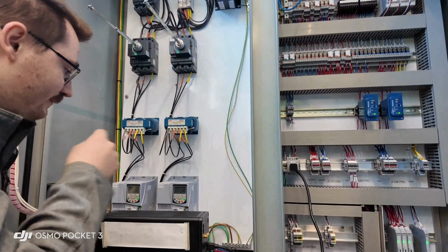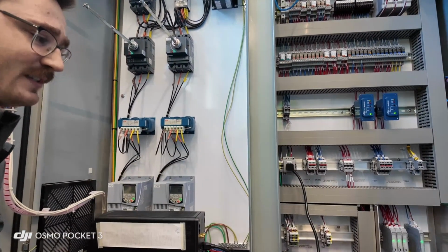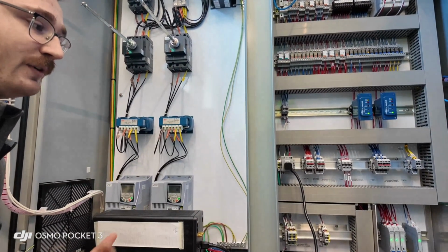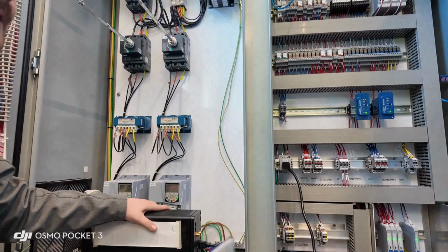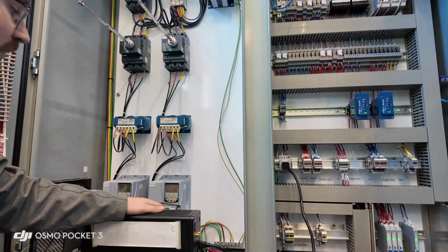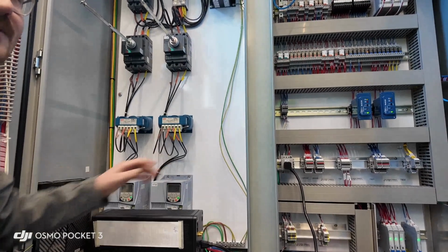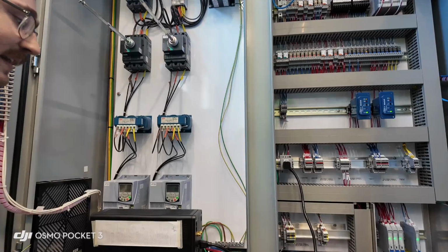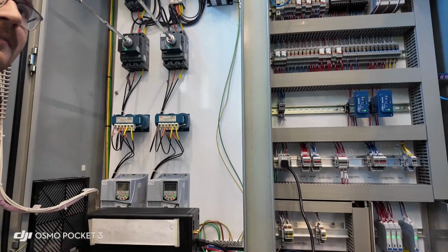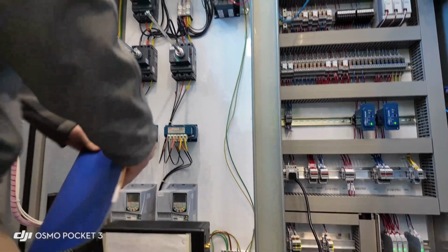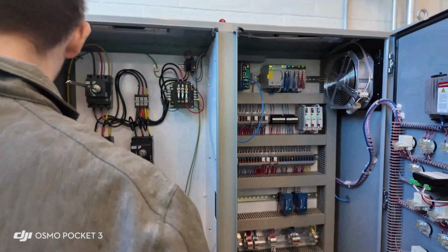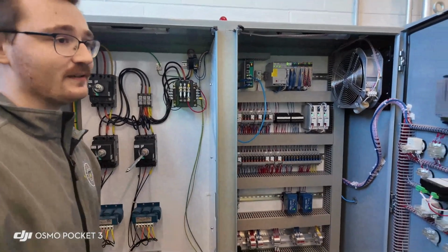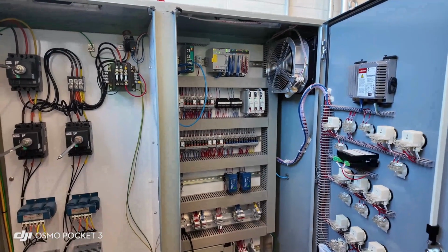When you replace that module, it kind of limits how much I/O you can get from it, but you're able to communicate Ethernet. If you ever need additional signals, like say, what's the amperage? I want to see what type of amperage it's running at, or like hertz, stuff like that. You can tell it through PLC programming, like additional signals in front of it. It also shows it right on HMI, but if you want to see it, just go to this. I think it can be sent over through Ethernet.